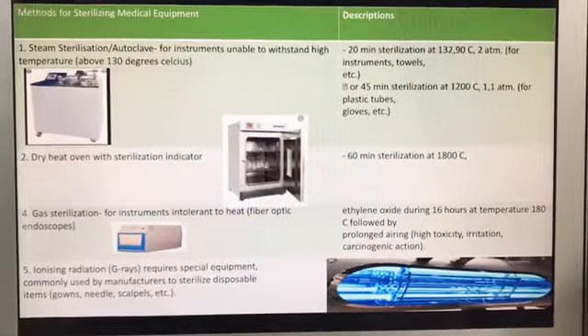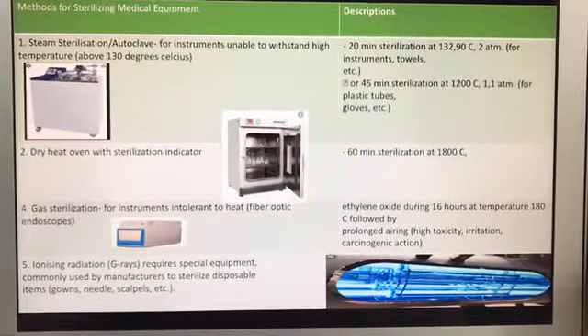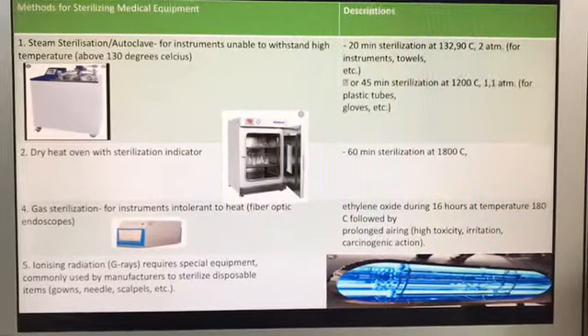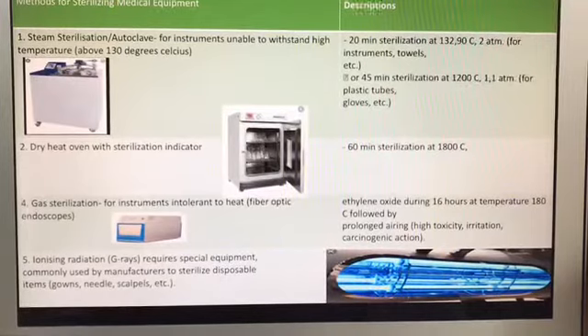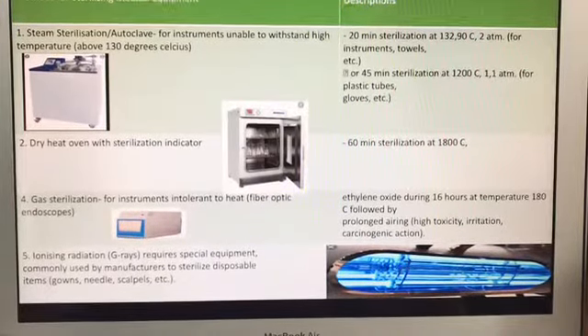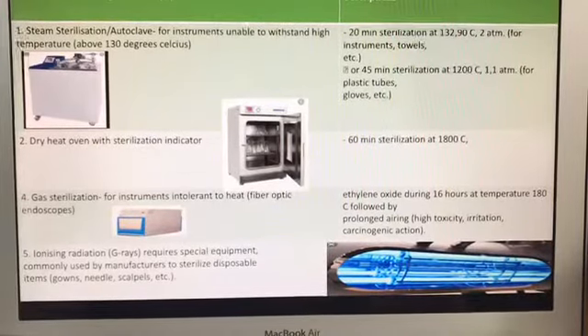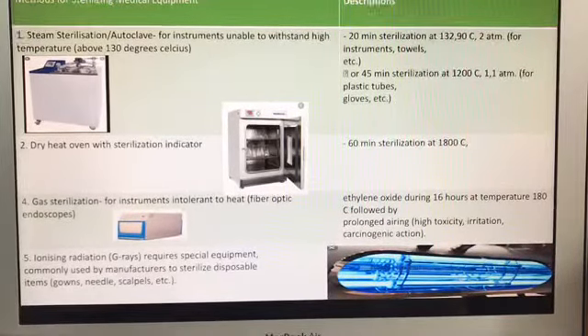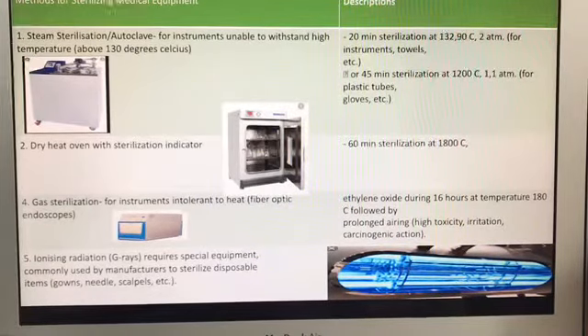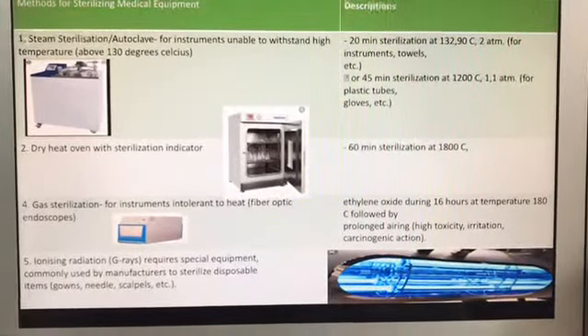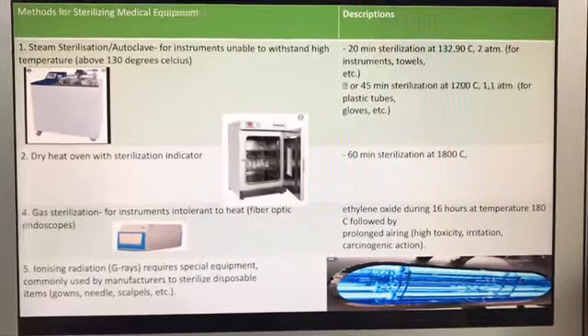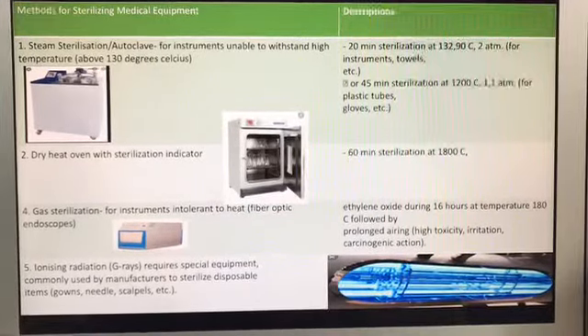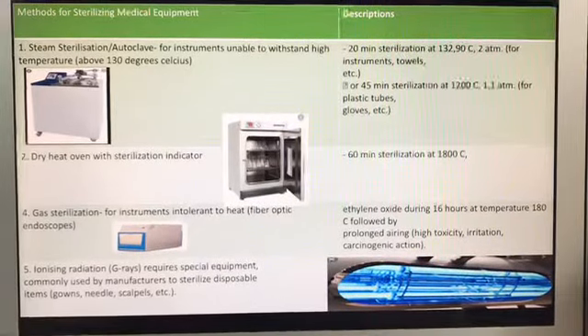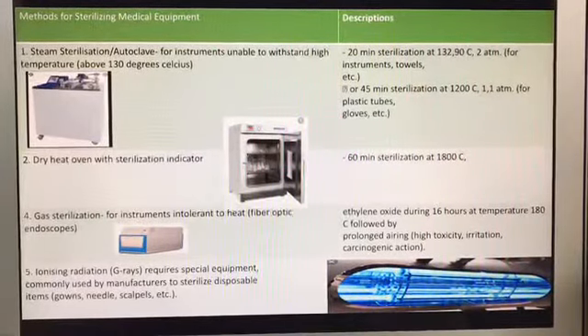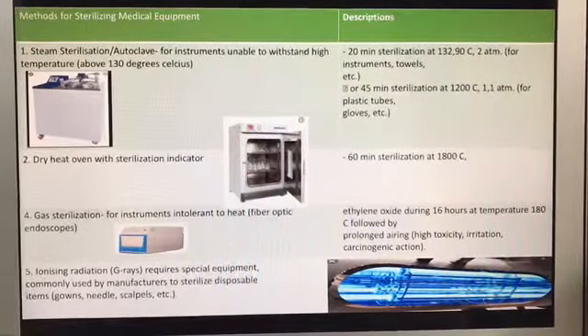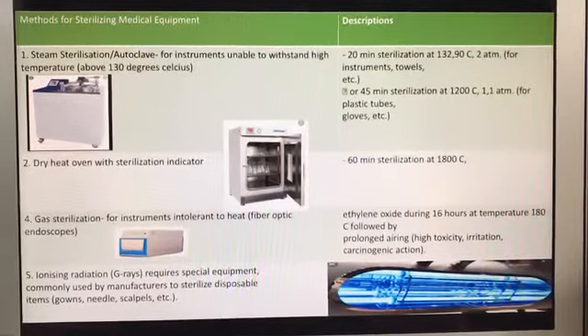For steam sterilization, most sterile processing departments have steam sterilizers called autoclaves, because steam can clean many common medical devices and is typically the safest and cheapest option. Some technicians will only consider using another method when the medical device is made of a heat-sensitive material and cannot be steam sterilized. The autoclave applies intense pressure and heat to destroy all the microorganisms on the objects. As you can see, it is not for instruments unable to withstand high temperatures above 130 degrees Celsius. My colleague will be discussing the autoclave methods in another video.